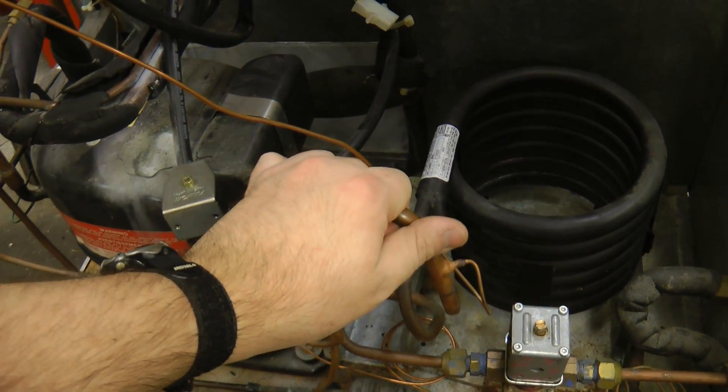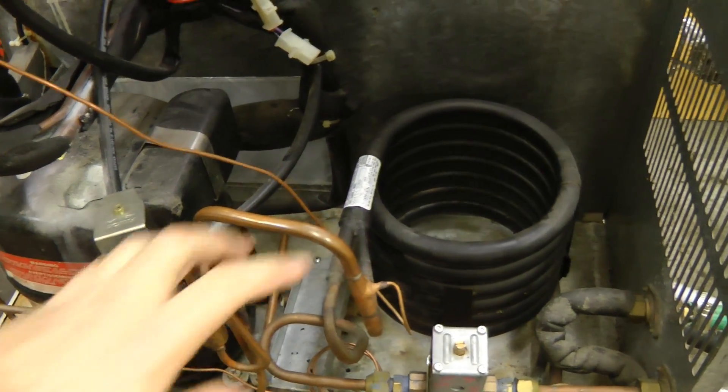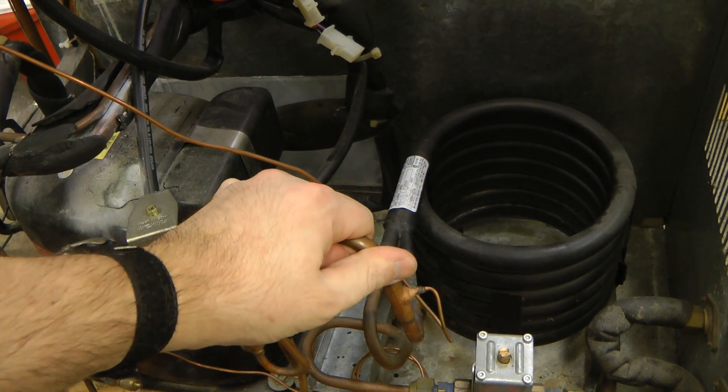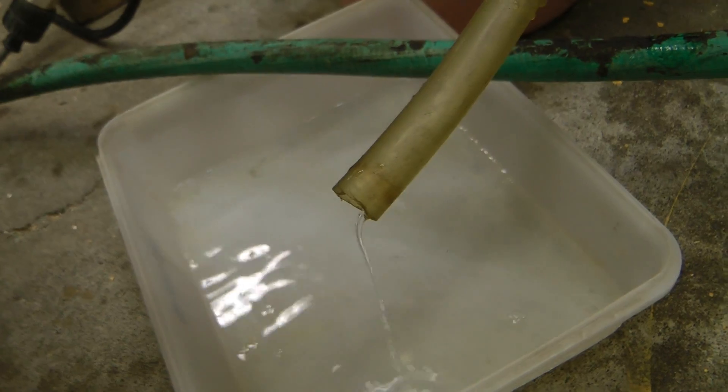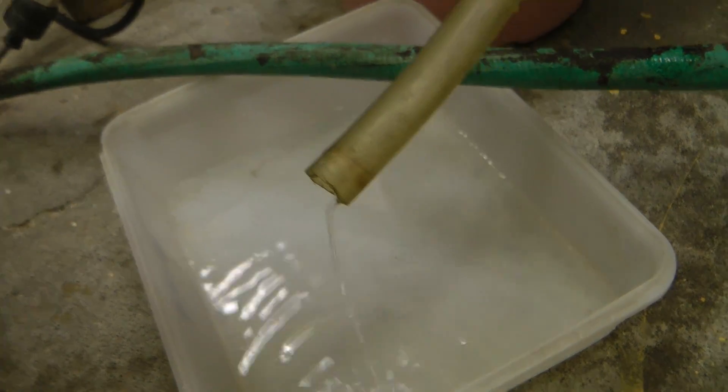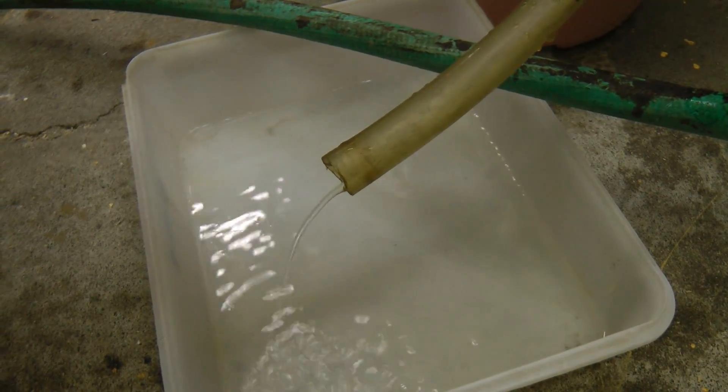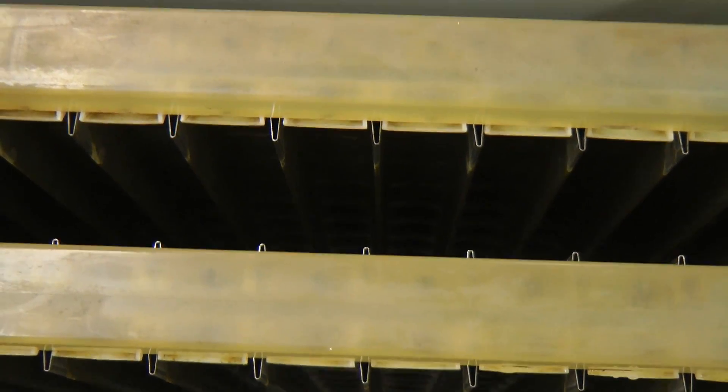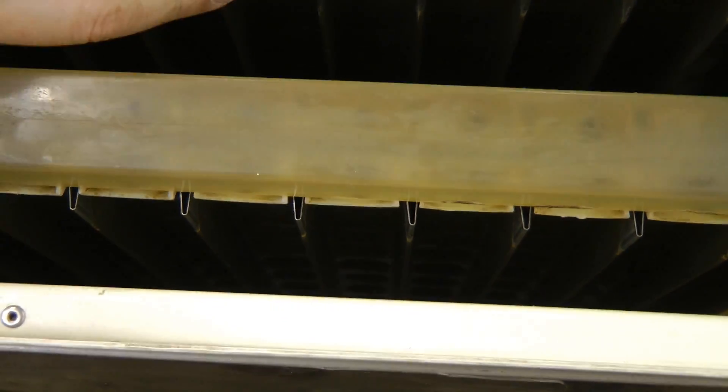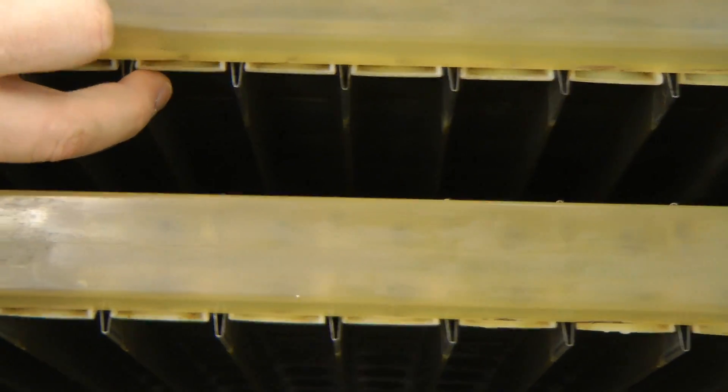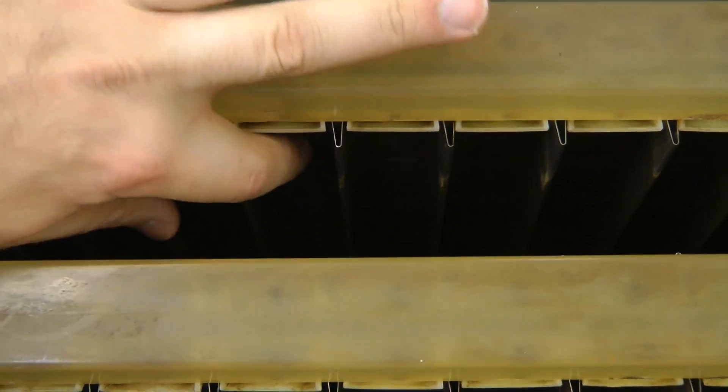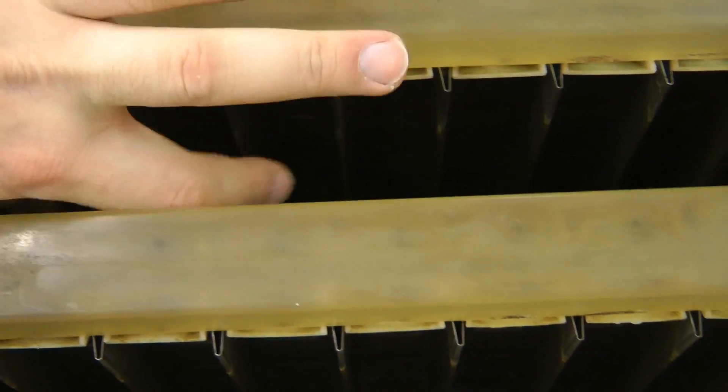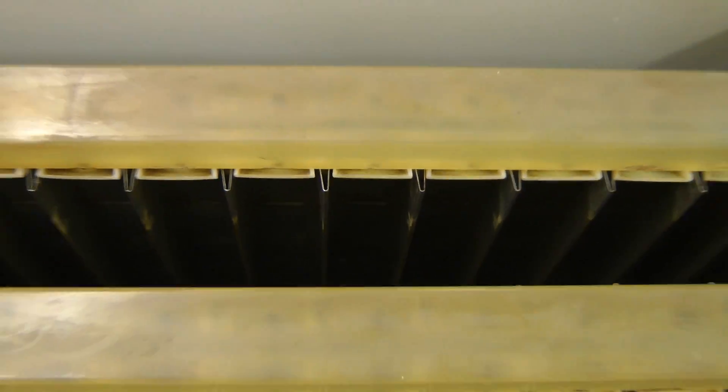I'm guessing as the ice fell down it tends to break that grill. It seems to be making a little bit of cooling although I'm not sure if that's just the cold water. The pressure discharge is getting a little bit warm. I'll give it five or ten minutes and then we'll see how it's running. Right now the bypass valve is barely flowing anything. Apparently this machine produces crescent-shaped ice cubes rather than the square ones. That's probably why they're using a low thermal conductivity material here so the ice will just build up where the tube contacts the plated stainless steel rather than all over the whole thing, so it'll form crescent shapes.